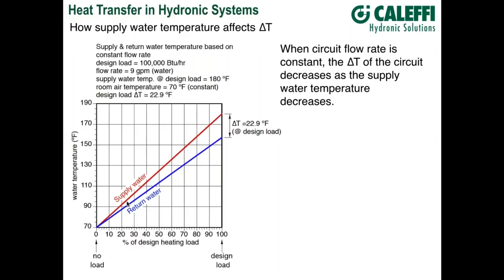That delta T is the temperature difference between supply water temperature and room air temperature. This is the basis of outdoor reset control — as the heating requirement of the building goes down based on warmer outdoor temperatures, we can reduce supply water temperature and still maintain stable indoor temperatures. The advantage: as we go to lower temperatures, modern heat sources experience increased efficiency — mod-con boilers, almost any renewable system gives better efficiency at lower water temperatures.